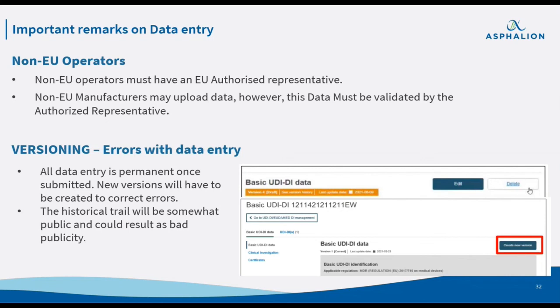Also, for traceability purposes, the EUDAMED database does not allow editing data. This means that new versions of the complete register have to be created every time a change is made, and it is really important to track all these changes, because once you carry out a new submission, you will have to provide the number of the previous version you were uploading. Also, it's very important to consider that public viewers can see in the public domain how many versions of each register you have.